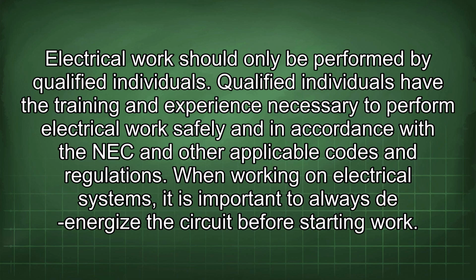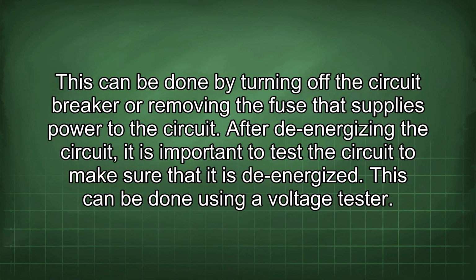When working on electrical systems, it is important to always de-energize the circuit before starting work. This can be done by turning off the circuit breaker or removing the fuse that supplies power to the circuit. After de-energizing the circuit, it is important to test the circuit to make sure that it is de-energized. This can be done using a voltage tester.